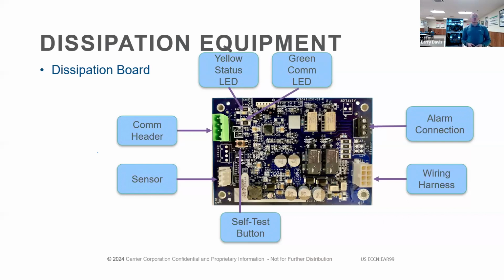And if you're on a communicating system, you still have that ABCD communication plug that you will use. On the communicating system, and you'll see this a little bit later as well, if it's a 454B system and you're using a communicating wall control, it's not going to run until it finds its dissipation board. So you have to wire it up for communication.